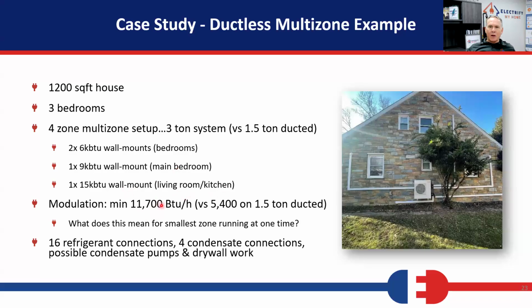The modulation minimum on this is 11.7 versus 5,400 on a 1.5 ton ducted. So if I have a 1.5 ton ducted, it'll reduce the entire load for the entire house down to 5,400 at its lowest point. So once I get the house conditioned, I can keep the house conditioned using a tiny bit of energy. This thing never is going to go below 11.7. That is twice as many watts when we look at it. So when this thing is running in its lowest stage, it's going to use twice as much energy as this does. So what does it mean for the smallest zone running at one time? We got 16 refrigerant connections, 4 condensate connections, possible condensate pumps, and a bunch of drywall work versus just putting a 1.5 ton ducted in.